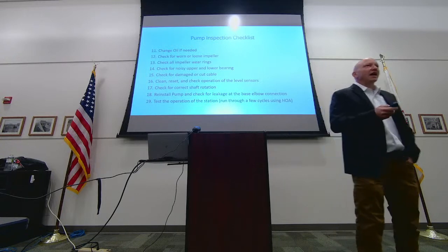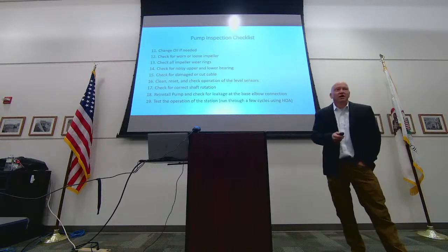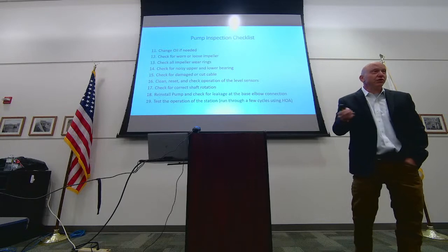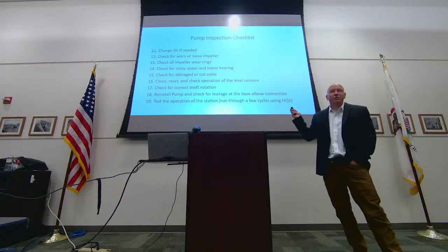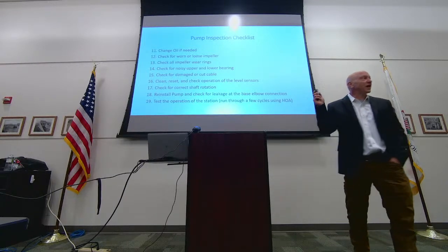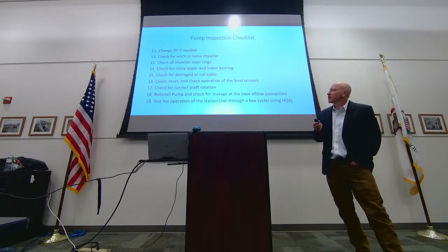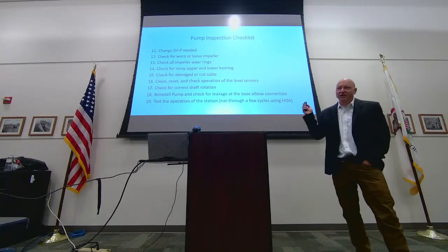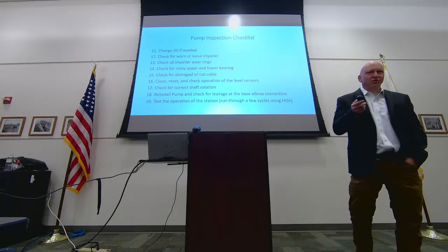I had a new installation and had just been in there 6 months. Got it back to the shop. They're like, we want to make sure this is under warranty. I'm like, well, there is a warranty in place here, but not on the cable. There's no warranties on cables because that's the first thing a contractor screws up. They'll catch the cable on something, or they'll set the pump down on the cable. It'll cause that. Now, in this case, the contractor knew he had done something because they wrapped the crap out of the cable with electrical tape.